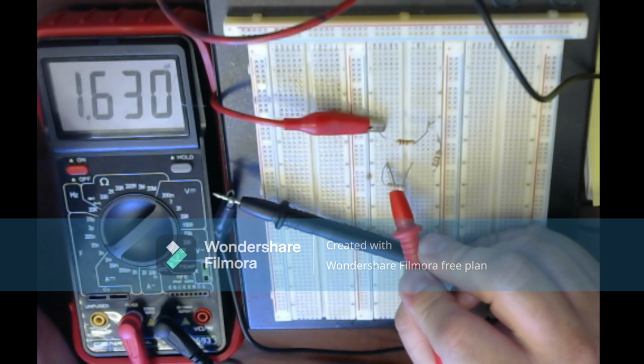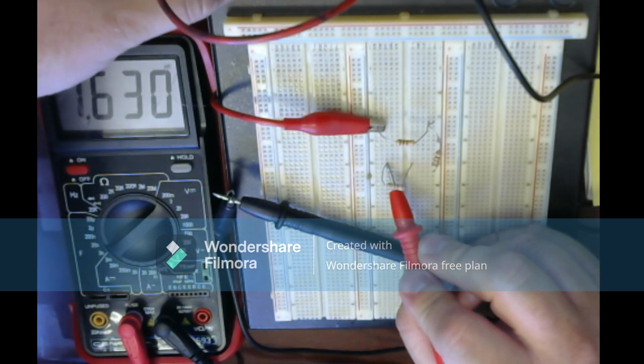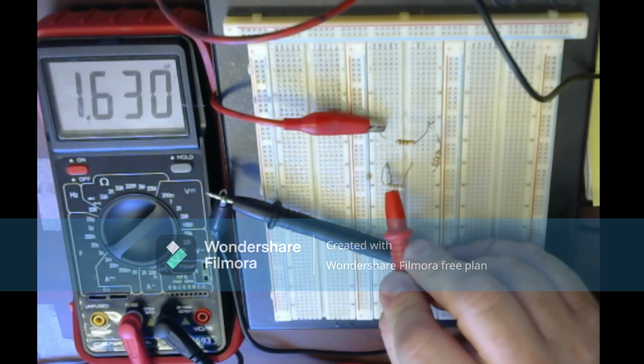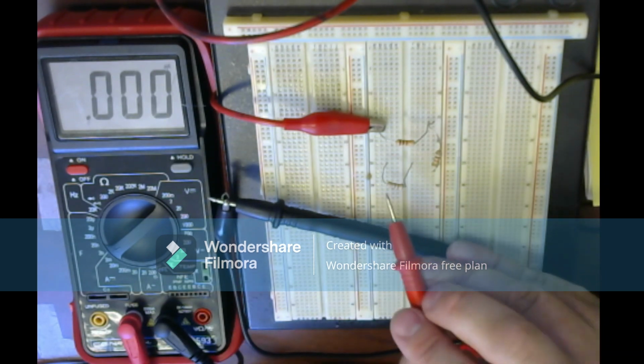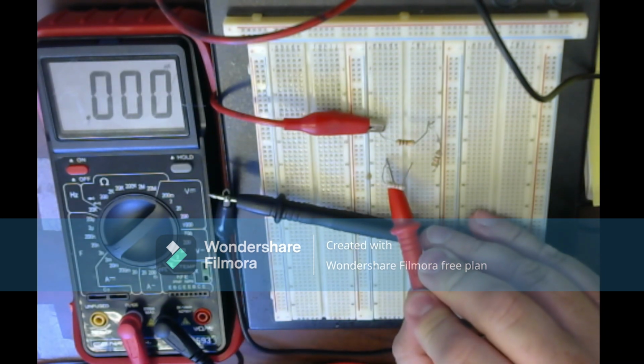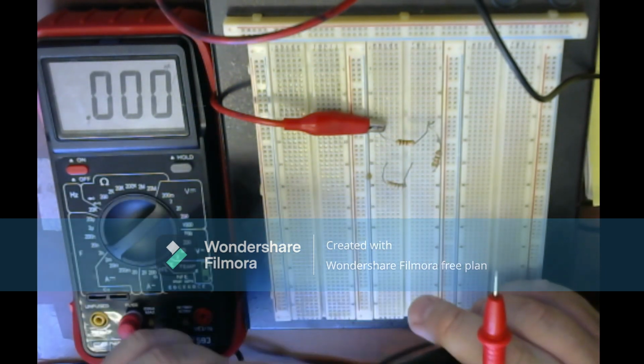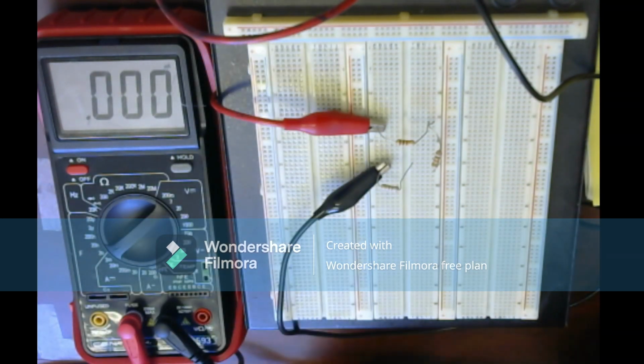Now, if I wanted to look specifically at a component, I'm going to shut my circuit off and disconnect it. Make sure we're dead, we should be reading 0. I'm going to take my meter, disconnect it, and put it back to where my circuit was.